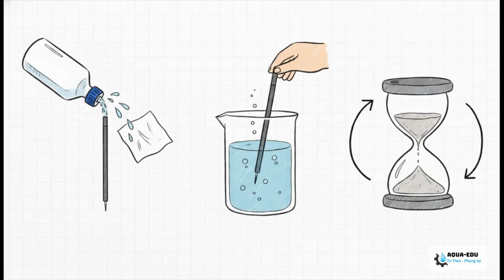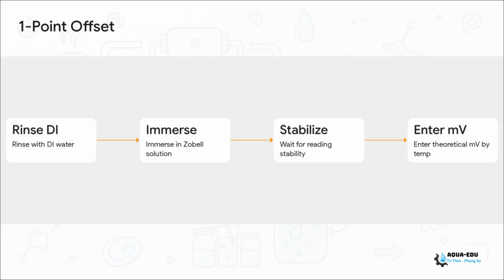It usually takes about 60 to 90 seconds until the reading stabilizes within a tight 2 millivolt range for at least 30 continuous seconds. Once it's completely stable, you're going to enter the offset calibration mode on your transmitter. This is where you input the theoretical value. So for a silver/silver chloride reference, ZoBell is typically plus 228 millivolts right at 25 degrees Celsius. Enter that into the transmitter and hit confirm. The transmitter is going to calculate the offset adjustment. Now that offset adjustment absolutely must fall within plus or minus 10 millivolts.